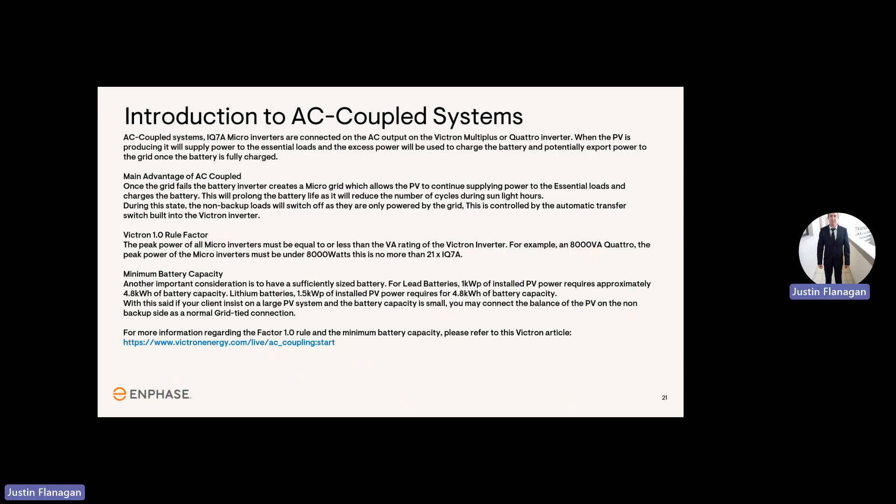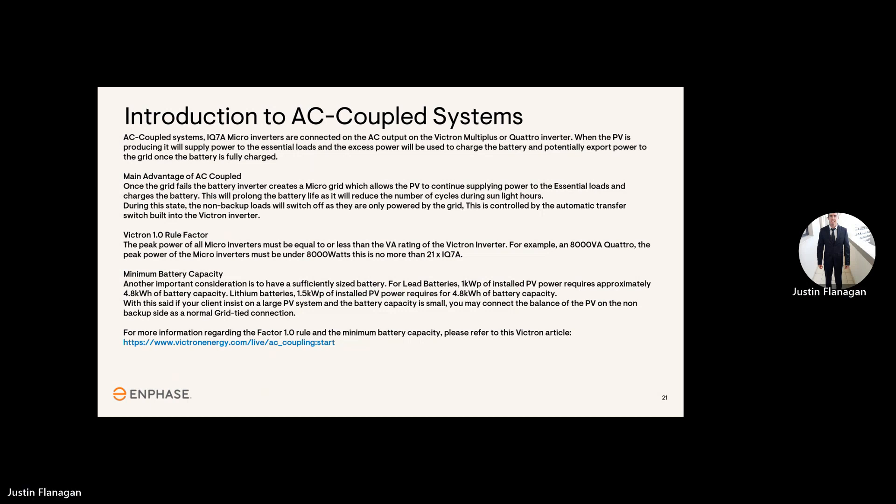Introduction to an AC coupled system. IQ7A microinverters are connected on the AC output of a Victron MultiPlus or Quattro inverter. When the PV is producing power, it will supply it to the critical loads and excess power will be charged to the battery when there's no grid available. The main advantage of AC coupled: once the grid fails, the battery inverter creates a microgrid which allows the PV to continue supplying power to the critical loads and charges the battery. This will prolong the battery life as it reduces the number of cycles during sunlight hours. During load shedding, the non-backup loads will switch off as they are only powered by the grid. This is controlled by the automatic transfer switch built into the Victron inverter.